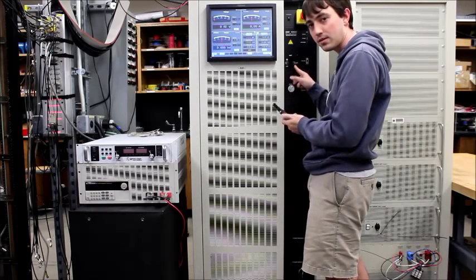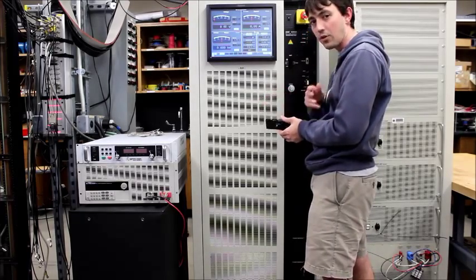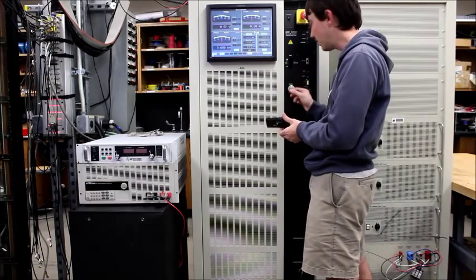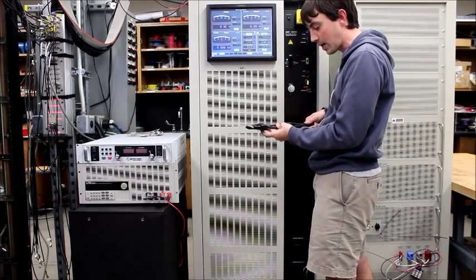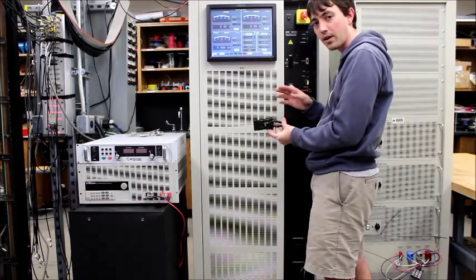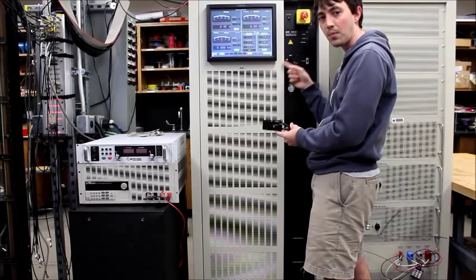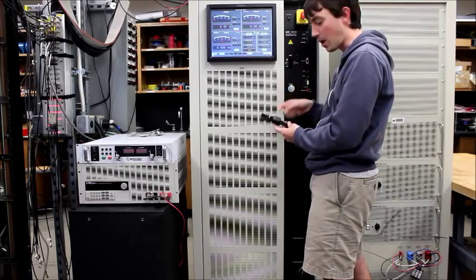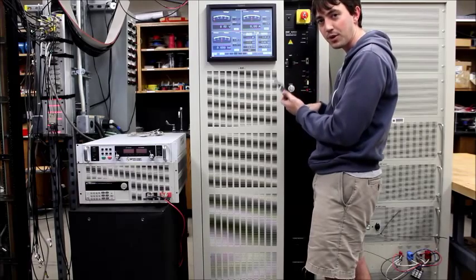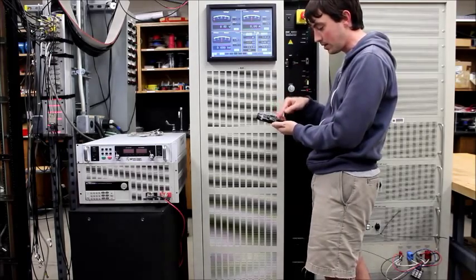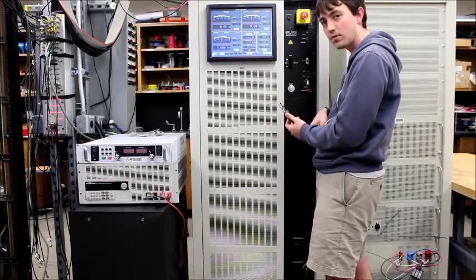The other one is an external sense. If your power supply was in like another room and you wanted to test down the hallway, you could run a parallel sensor wire down the hall in parallel with the main power cable. And then you would be able to measure with pretty good accuracy the terminal voltages in the other room and the unit would compensate for that voltage drop across the main power cable. So the external sense, it's right here. So if you don't have a long cable, I've just made a jumper between the main power cable and the external sense. So there's two little jumpers inside this plug for the external sense wire.